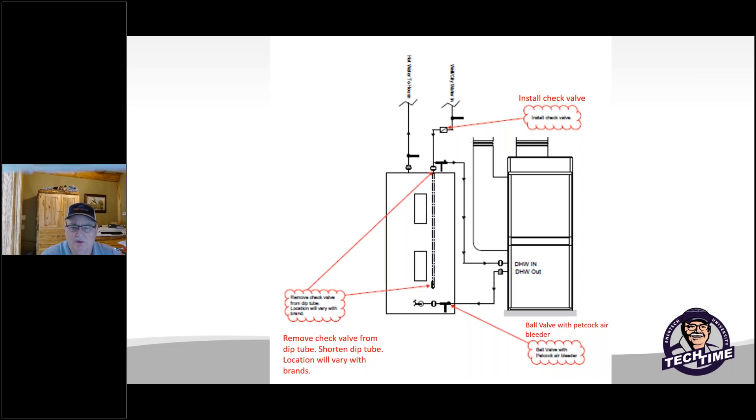A typical one pump system to a one storage tank may look similar to this. The one thing that most water heaters, if you use one of these, have a check valve built into the inlet and they're typically connected inside down below the fitting in the dip tube.